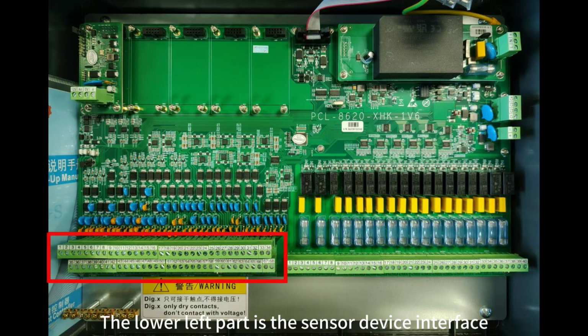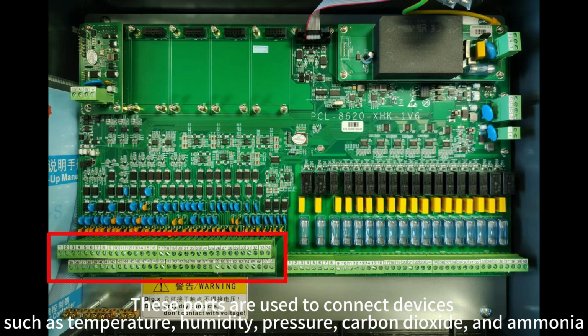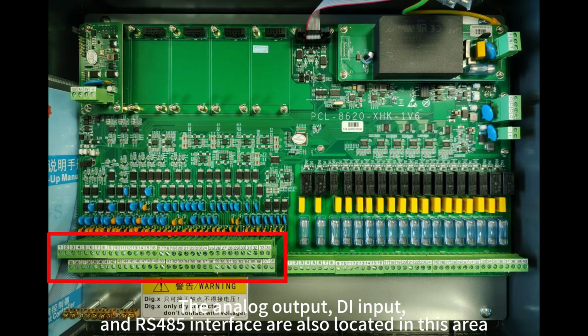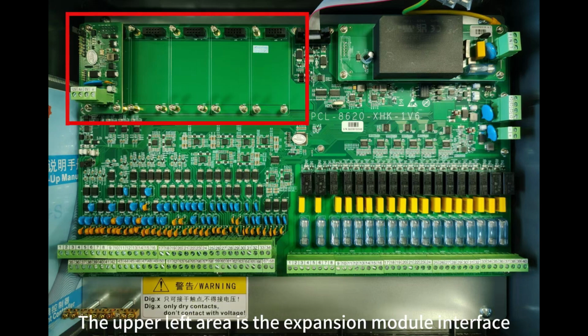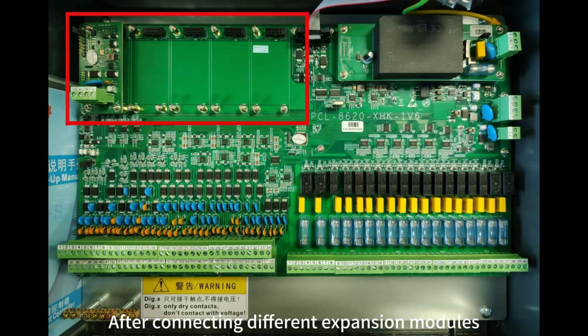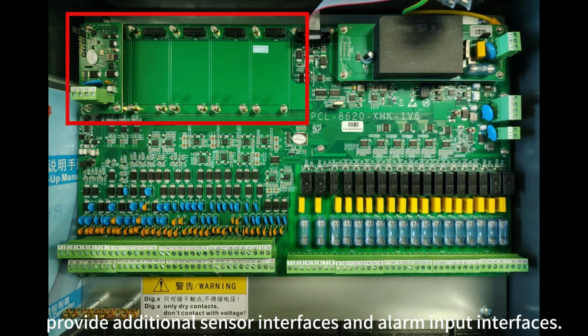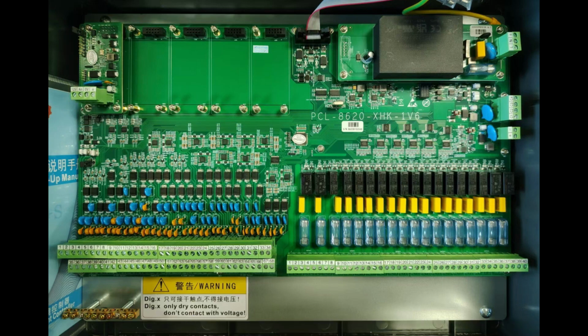The lower left part is the sensor device interface. These ports are used to connect devices such as temperature, humidity, pressure, carbon dioxide, and ammonia sensors. The analog output, DI input, and 485 interface are also located in this area. The upper left area is the expansion module interface. After connecting different expansion modules, it provides additional sensor interfaces and alarm input interfaces.